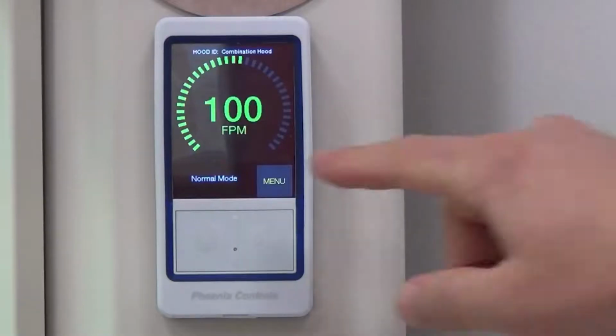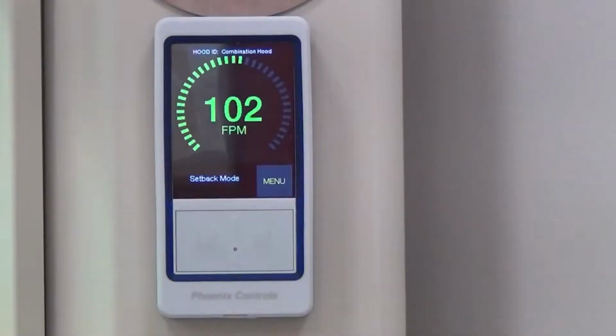So we added this energy meter on the screen to basically show when the fume hood is at its normal operation or when it's in setback. It has a relative range on there for your minimum to your maximum airflow, as well as the fact that it displays the face velocity, or it can display the flow as well. The other nice feature about these is you can also change the screen so it's just an active or an inactive alarm or normal condition. So the screen would just be green or red if it was normal or an alarm, or you can have the face velocity or the flow displayed on the screen.